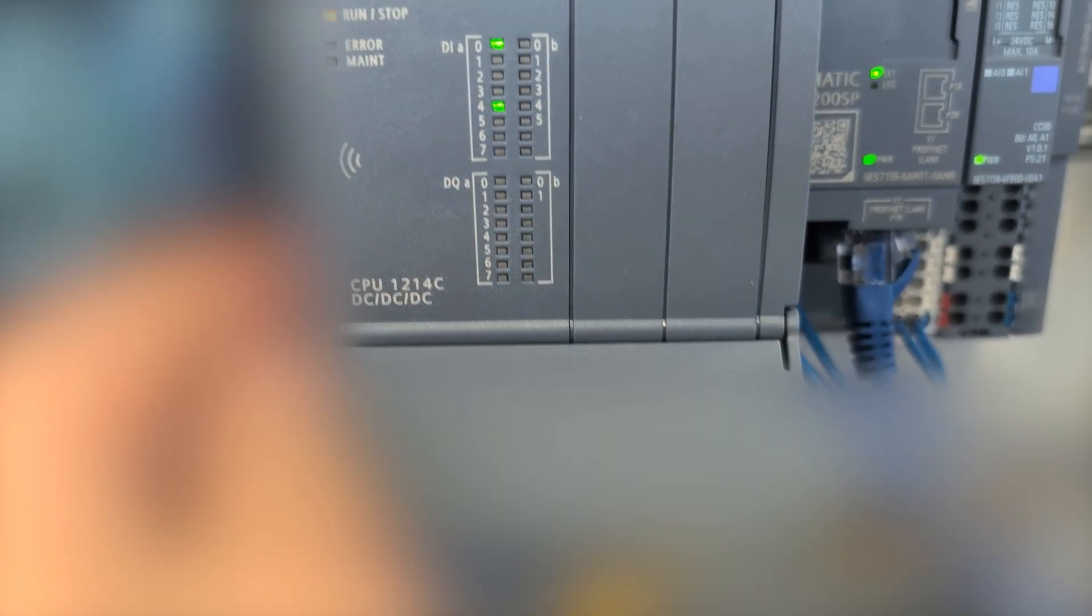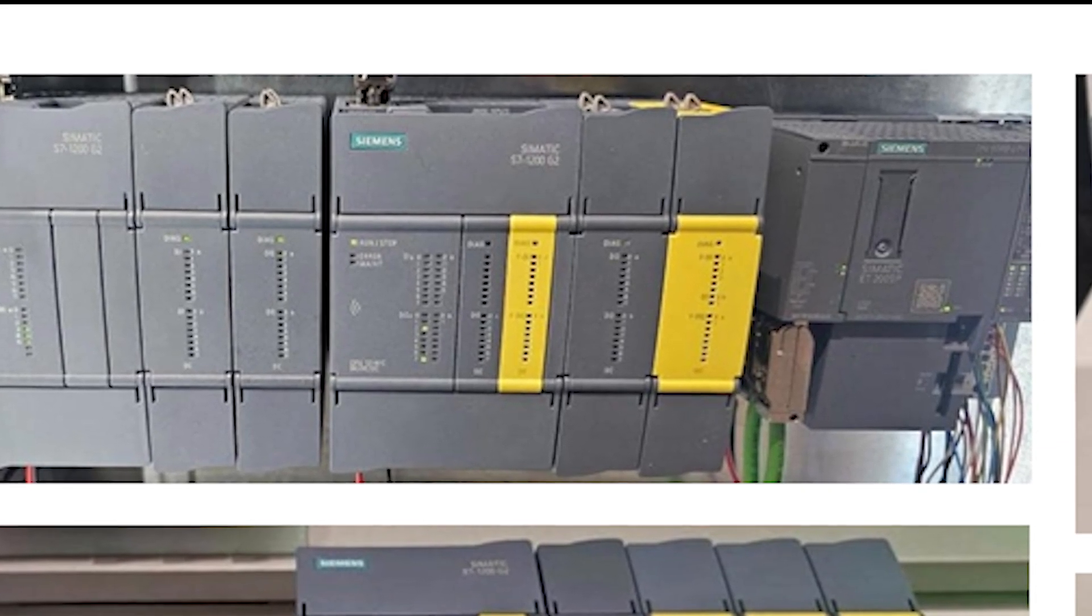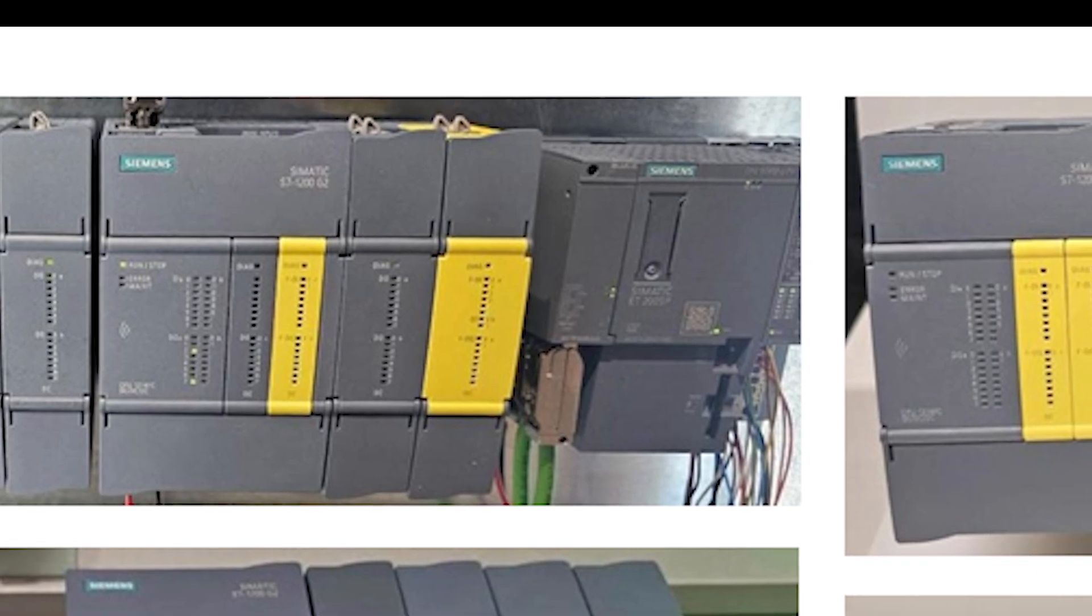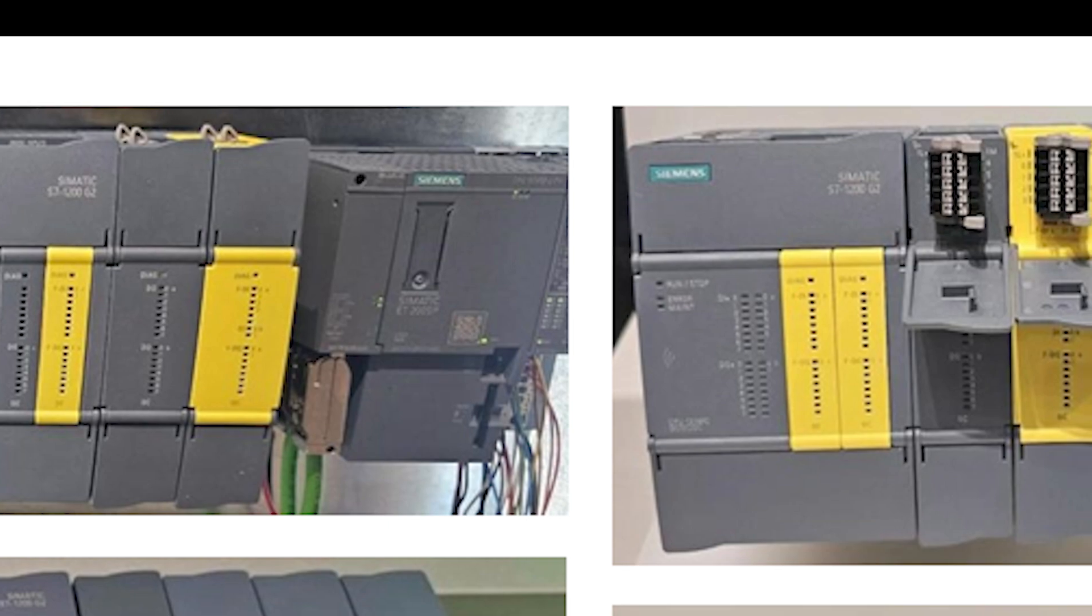I did mention the power connector. On the old 1200, when you're putting in your power, you're putting it on the top left, and then you've got your digital inputs. On this one now, they've got three connectors, three push fit connectors. So one push fit connector at the top does digital inputs and then you've got two at the bottom. One does power and that does power supply input to your PLC and it also does the power supply for your outputs, your DQs. So that's one whole separate connector, which I love because when you're messing about with the AC 1200s, it was always a bit scary. You've got 230 volts and you've got 24 volts right nearby. So having it just on one whole complete separate connector is quite cool. The push fit is kind of hit or miss. I like, personally, the screw terminals where you've got to screw in the wires, but I can see the appeal for the push fit connectors, to be honest with you. I did struggle a bit using them today, but yeah, it's fine.